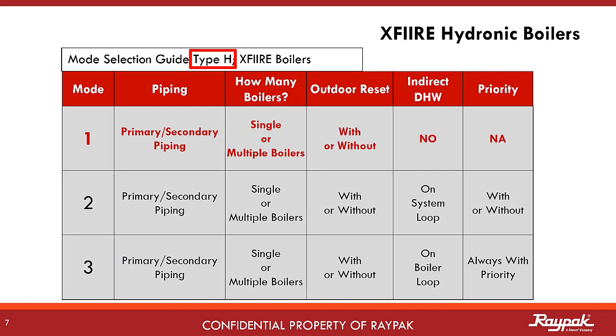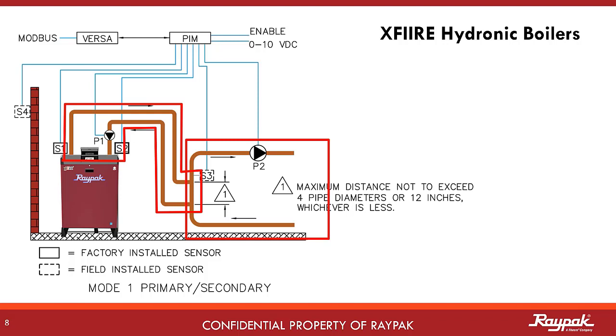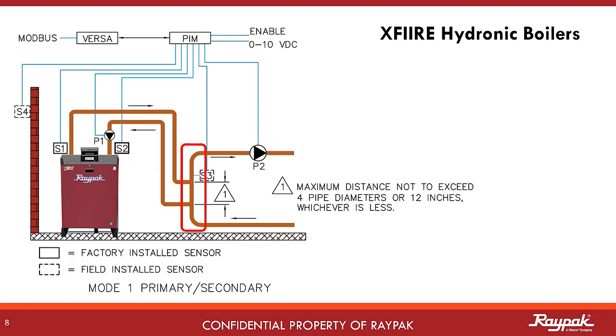First, we will present Mode 1. Primary-secondary plumbing is required — this is the most common configuration with hydronic type boilers. Here is a drawing for Mode 1 primary-secondary with a single boiler. It is primary-secondary because there are two loops: the boiler loop and the system loop. The place where the two loops overlap is the decoupler. It is in Mode 1 because of what is not here — there is no indirect domestic hot water system present.